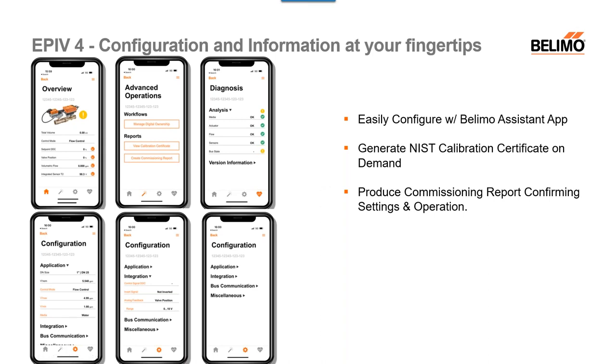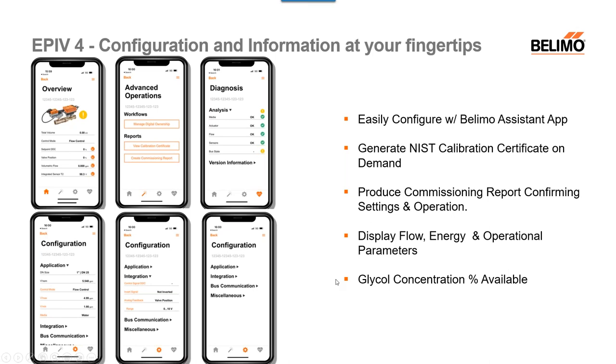Within the app, you can check and confirm settings and operations, make adjustments if needed. The app can display flow and energy data, operational parameters — you can change your VMAX and VMIN, change the media type in your system, so if it was set up for water but you have glycol, you can change that right then and there. The glycol concentration percentage is also configurable. All of this can be done through the Belimo Assistant App, so I highly recommend using NFC.